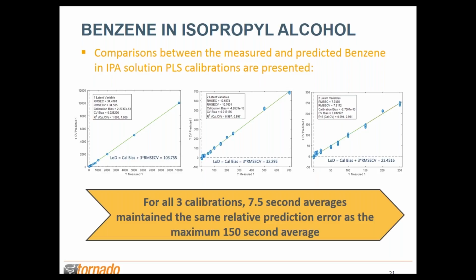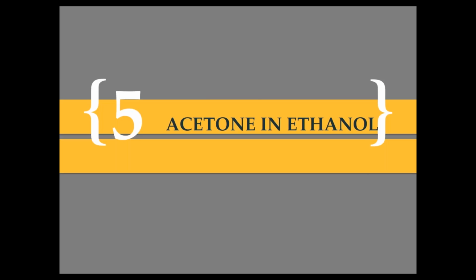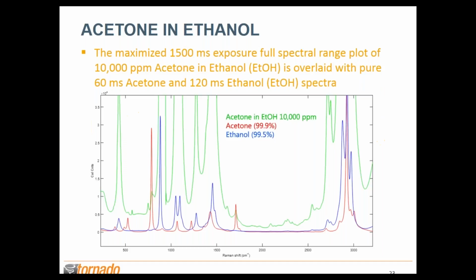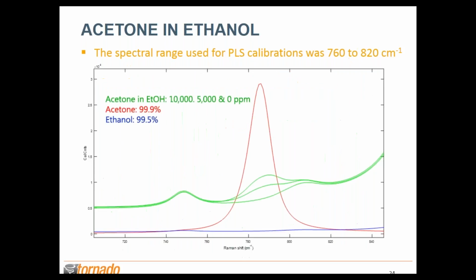Next, looking at acetone and ethanol. The plot provided below is the maximized 1500 millisecond exposure of the 10,000 ppm acetone and ethanol sample spectrum, overlaid with the 60 millisecond acetone and 120 millisecond ethanol spectrum. From there, I determined that the calibration range that I would employ would be 760 to 820 wave numbers.